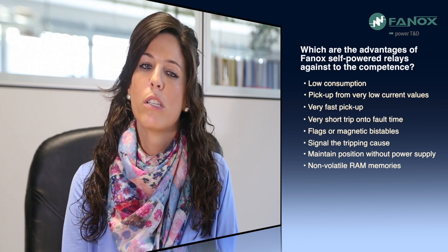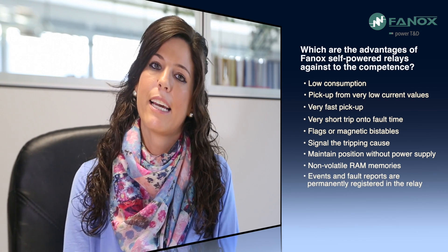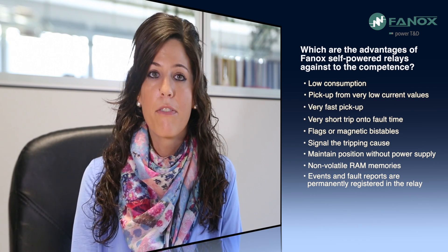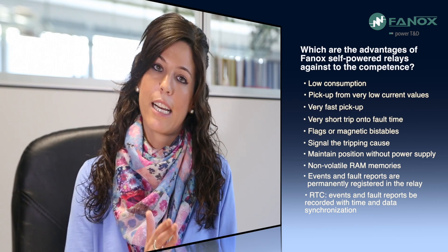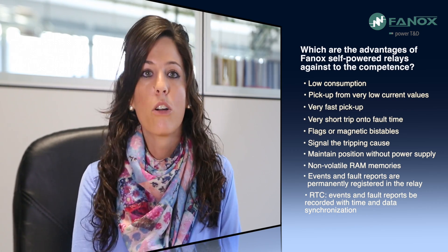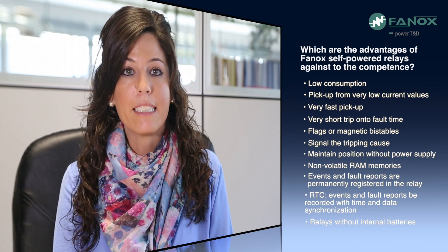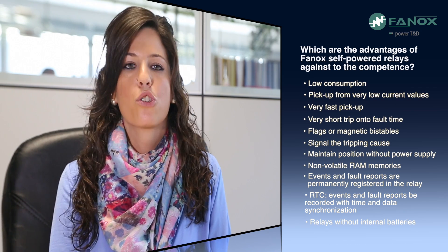Fanox self-powered relays have non-volatile RAM memories, meaning all events and fault reports recorded during relay operation are permanently registered. Combined with real-time clocks, events and fault reports are recorded with time and date synchronization — that is, they are stored with the exact time and date when they were registered. Finally, an important feature of Fanox self-powered relays is that they have no internal battery, because the self-powering concept means these relays are completely maintenance-free.